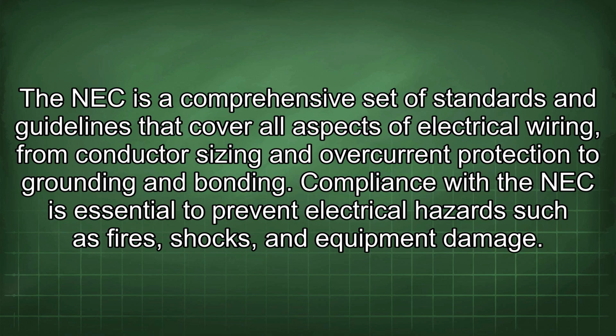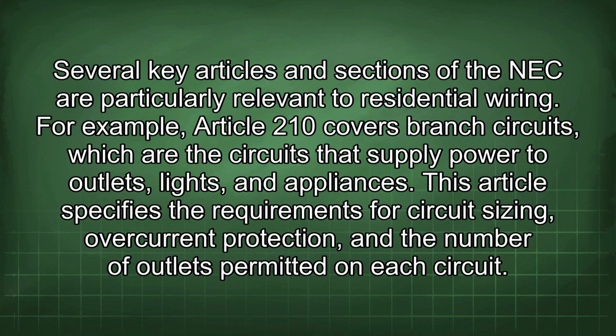Compliance with the NEC is essential to prevent electrical hazards such as fires, shocks, and equipment damage. Several key articles and sections of the NEC are particularly relevant to residential wiring. For example, Article 210 covers branch circuits, which are the circuits that supply power to outlets, lights, and appliances. This article specifies the requirements for circuit sizing, overcurrent protection, and the number of outlets permitted on each circuit.